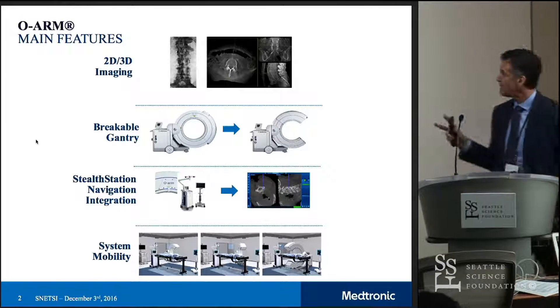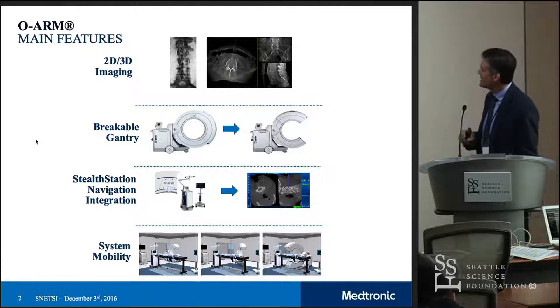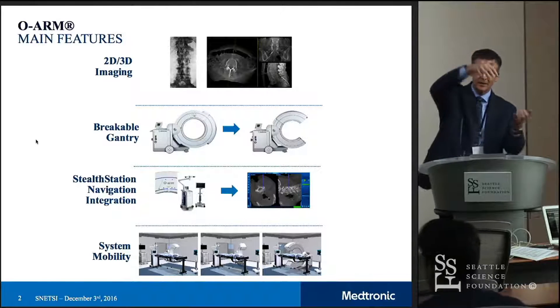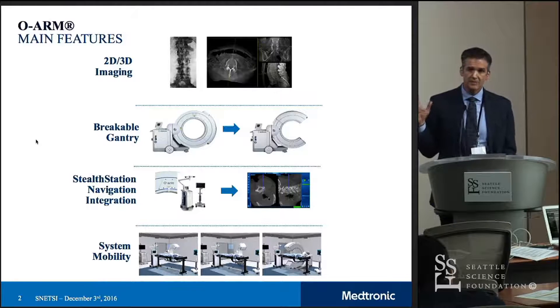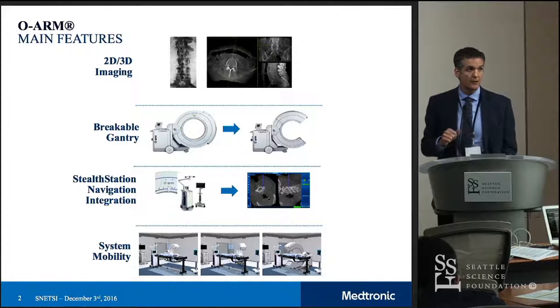For those of you who may not be familiar with the capabilities of the O-ARM itself, it's basically a 2D and 3D intraoperative imaging device. It has this unique attribute of having a breakable gantry so that it can access the patient laterally. You can come in, close the gantry over the patient, and then spin your radiation source and detector around that gantry. There is automatic registration capability built into this platform, and this was really one of the disruptive features of 3D intraoperative imaging, because prior to this there was a painstaking registration process that was necessary. This made it completely automatic and fully reliable.